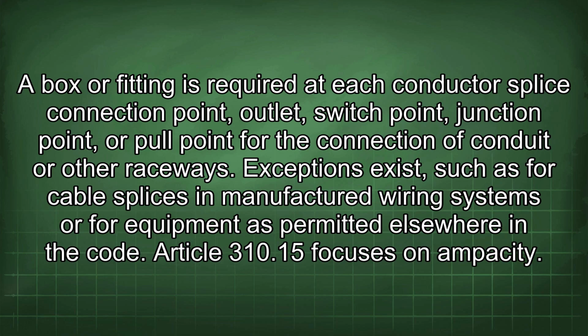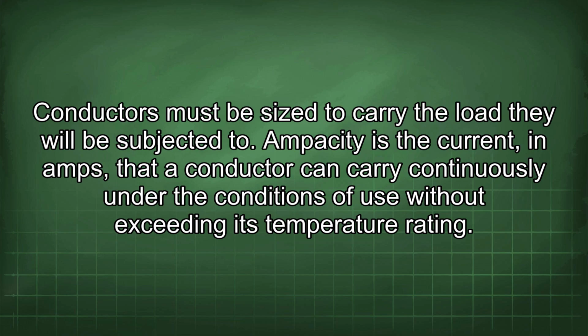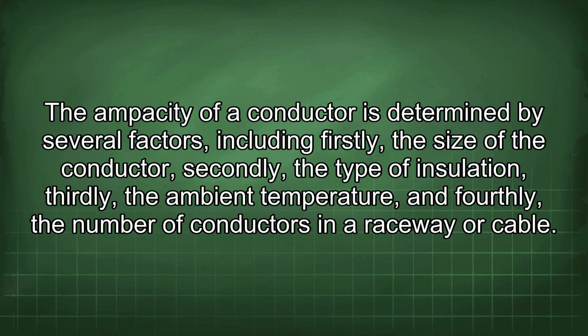Article 310.15 focuses on ampacity. Conductors must be sized to carry the load they will be subjected to. Ampacity is the current, in amps, that a conductor can carry continuously under the conditions of use without exceeding its temperature rating. The ampacity of a conductor is determined by several factors, including, firstly, the size of the conductor, secondly, the type of insulation, thirdly, the ambient temperature, and fourthly, the number of conductors in a raceway or cable.